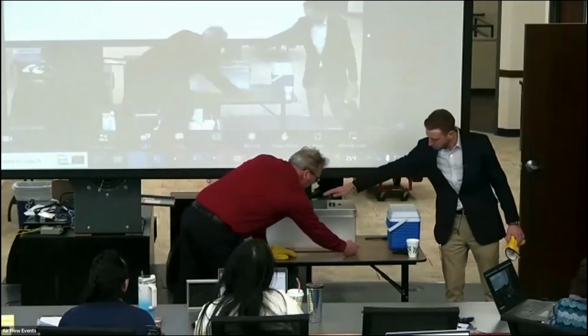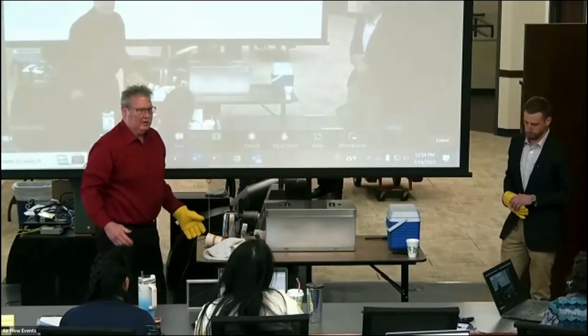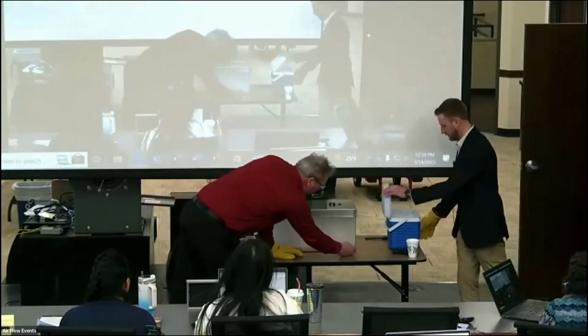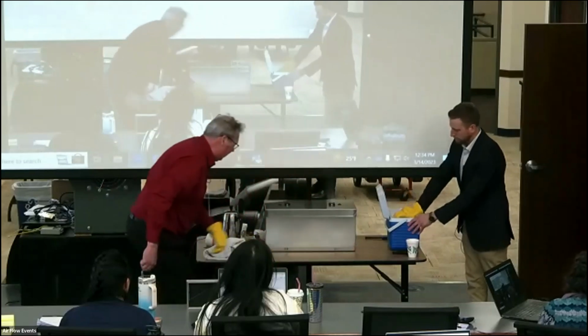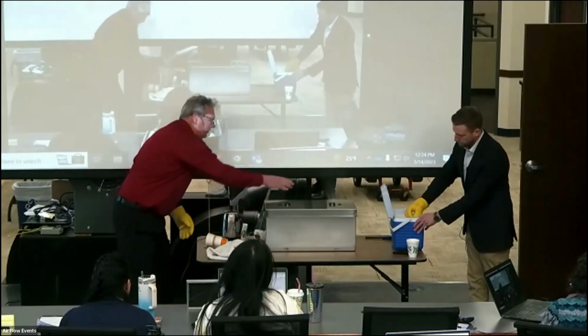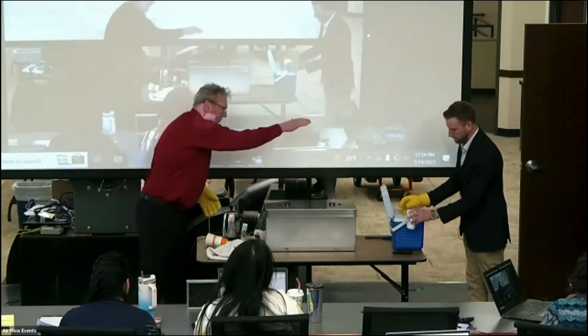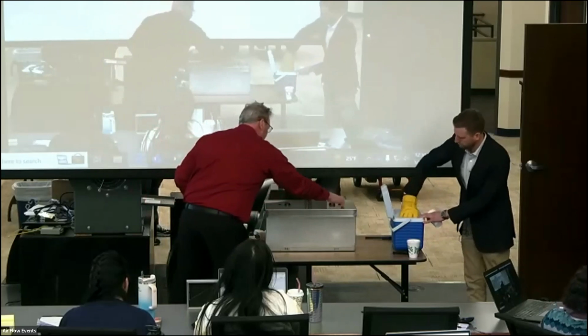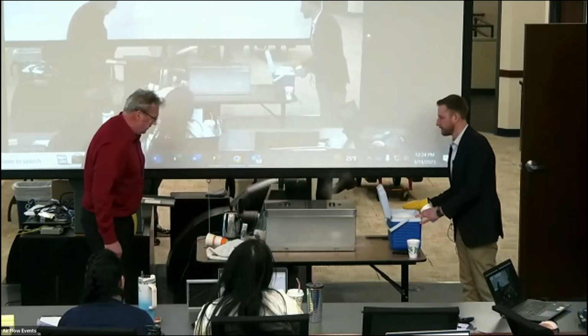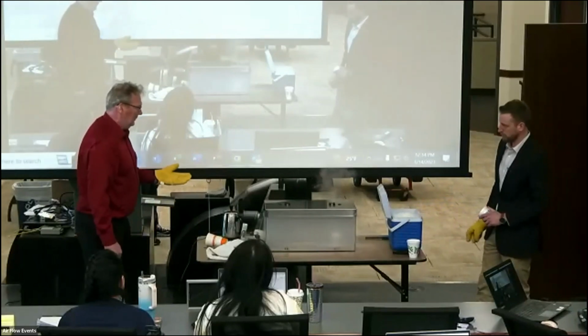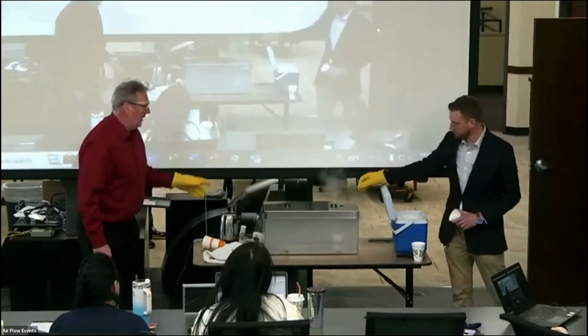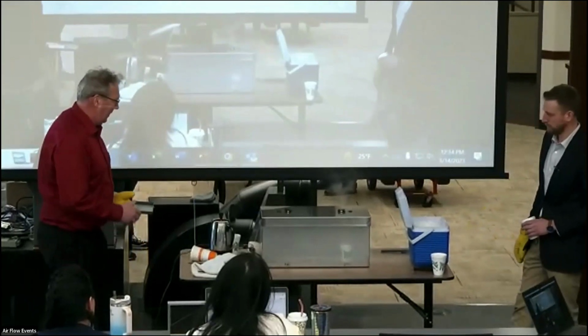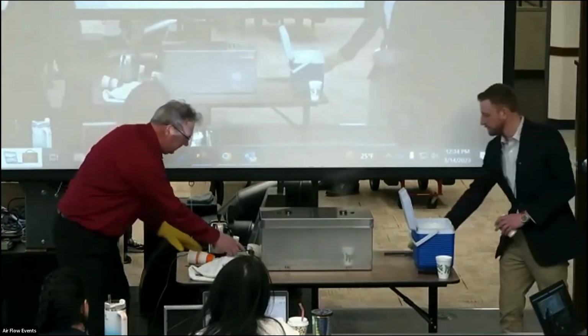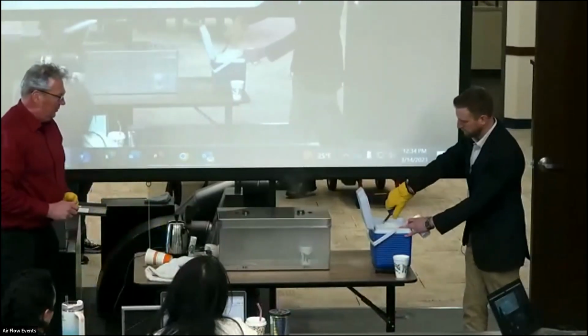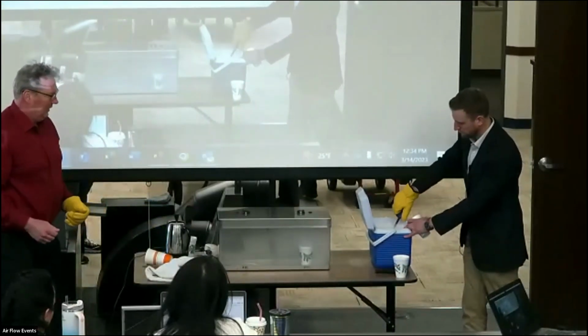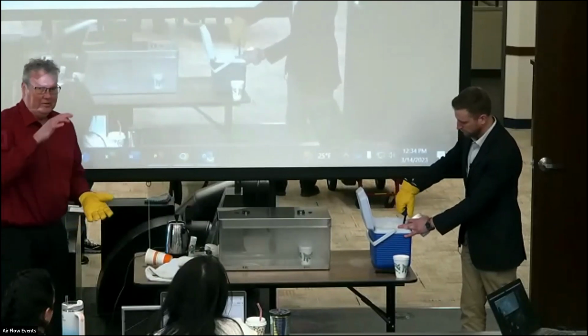Now you can see cracks in the building fabric like there is in any building. Older buildings are worse than new. Air is coming in and making a beeline right for that exhaust fan. See it coming in this side as well? And there's smoke coming out of the exhaust fan. You can see the height of the plume. Okay, let's try makeup air. Now you can see, for this experiment, more smoke coming out of the exhaust fan with it off than with it on. And there's also smoke coming out of cracks in the building fabric. Might be a leaky door seal, or where the roof meets the walls.